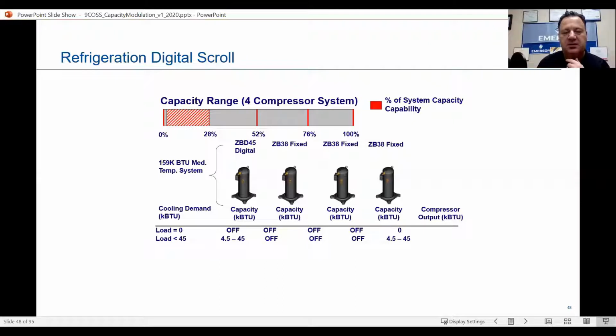When we're calling for this, when we get to the top of this 45,000 up here on the digital scroll, what's going to happen is by communication, it's going to tell the second compressor that, hey, I can't hold this anymore. I need help, as racks do, and it's going to come on. But the great thing about this is if we're already peaked out at 45, it's going to ask for help. The 38 is going to come on. Notice down here, the 38 is on now. This is going to ramp down, all right? It's going to load match.